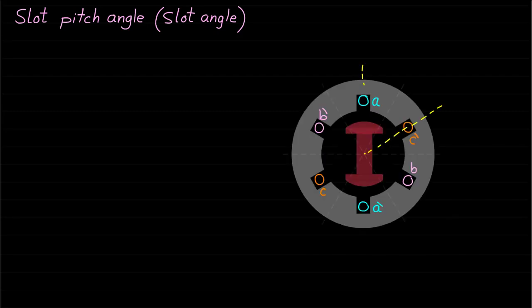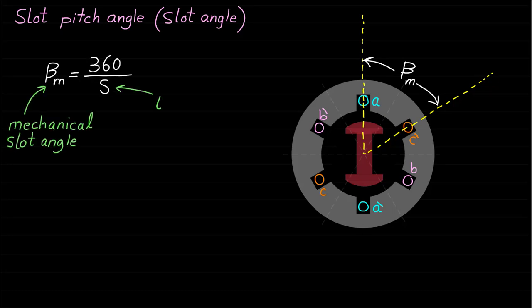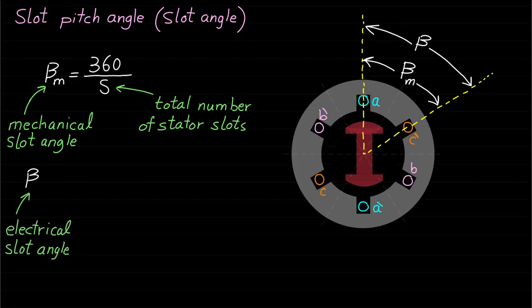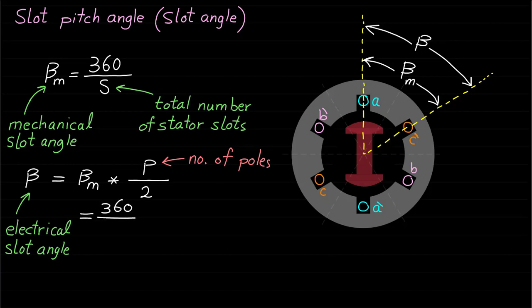Now let's learn the term slot pitch angle or slot angle. The slot angle is defined as the mechanical angle between two adjacent slots, denoted by β_M, and equals 360 divided by the total number of stator slots. The slot angle can also be represented as an electrical angle β, calculated by multiplying β_M by the number of poles over two. So the electrical angle β equals 180 divided by slots per pole. The electrical angle equals the mechanical angle only in the case of a two-pole machine.